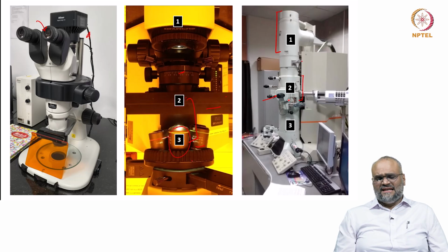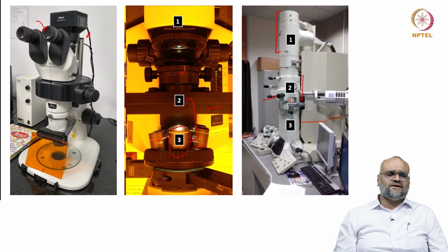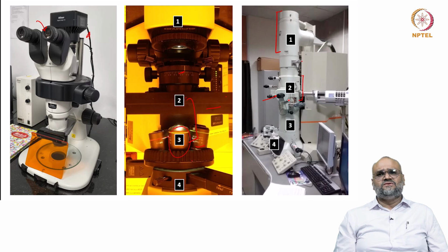But the lens here is actually a field lens, and by changing the strength of the lens, you are kind of changing the focus in the transmission electron microscope. And next we have the detection system. You typically use a CCD camera. You can see the image formed on the fluorescent screen here, which is behind this number 4. The fluorescent screen is somewhere here, and then the on axis or off axis recording cameras are below the microscope column. So this is the general layout of the microscope.